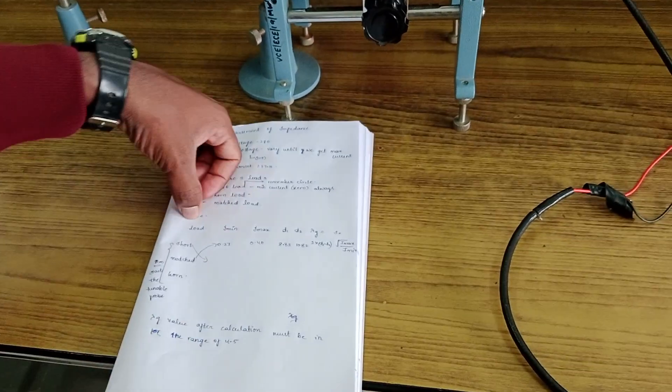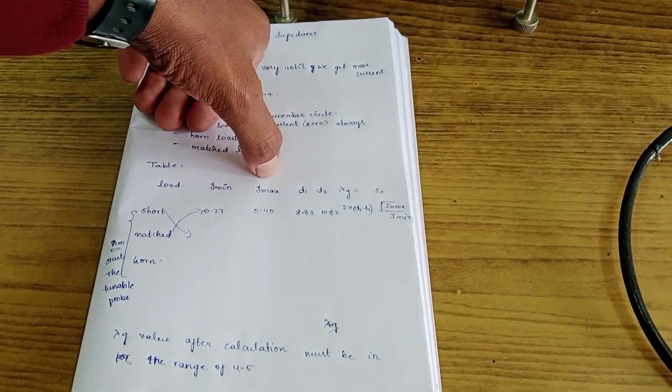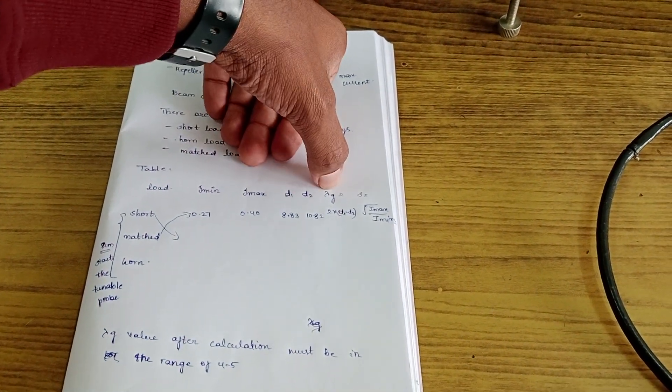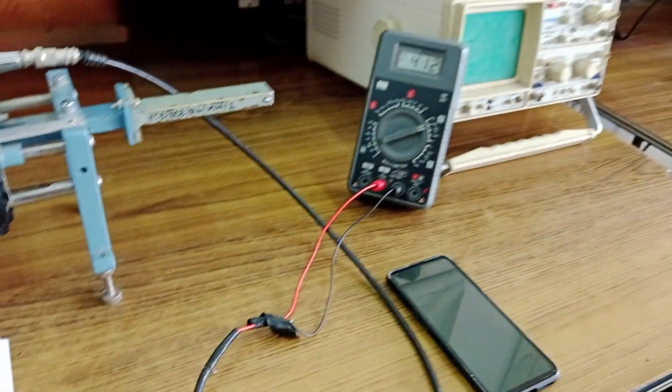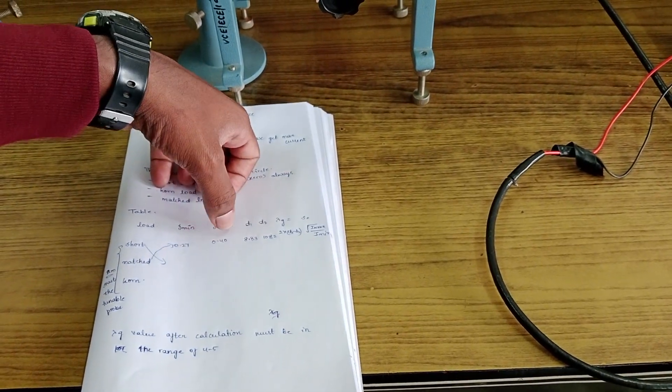So you have to maintain a table like this: Type of load, Minimum current, Maximum current, D1, D2, Lambda G, and S. The minimum current you have to note down what is the minimum current that you got in the overall measurement. Maximum current is the maximum current that you got in the overall measurement.